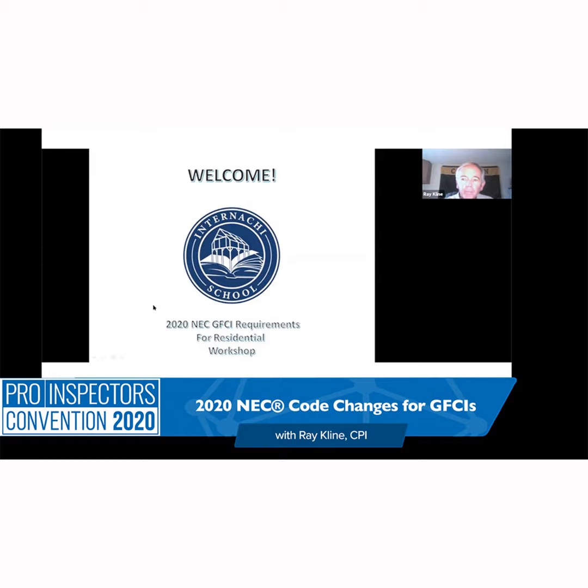Here I've got a picture of a three-prong plug-in tester. Here's a picture of a GFCI AFCI combo tester. I've got one of these. They work quite well. The only thing you cannot test with these is what's called pirated or stolen grounds on ungrounded systems, where they put a jumper on the neutral and jump it to the ground screw to try and fool you into thinking that it's actually grounded.